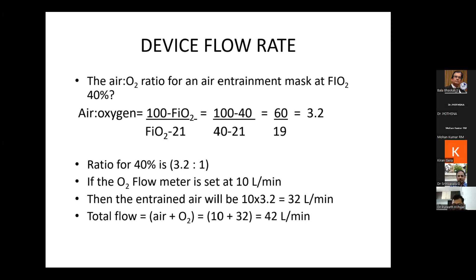And when we calculate the total flow, the amount of air entrained, when we add it to the flow meter flow, we will get the total amount of oxygen delivered to the patient. That is the flow delivered to the patient.